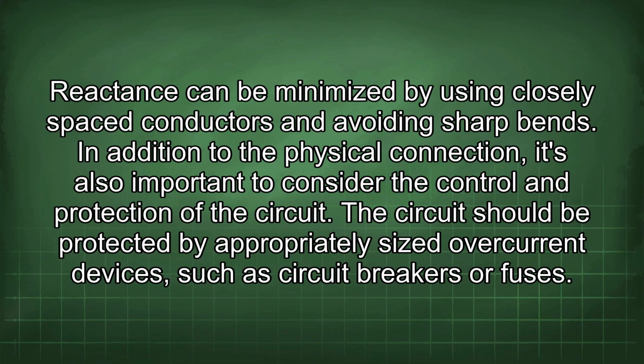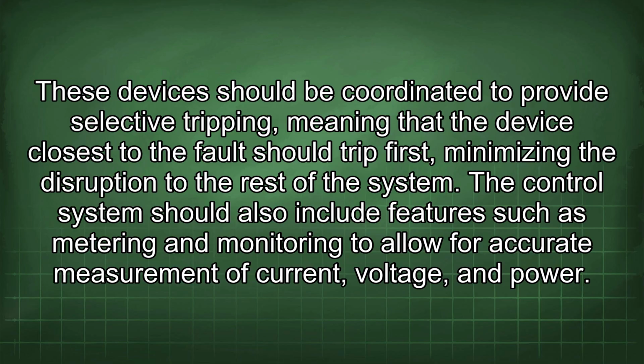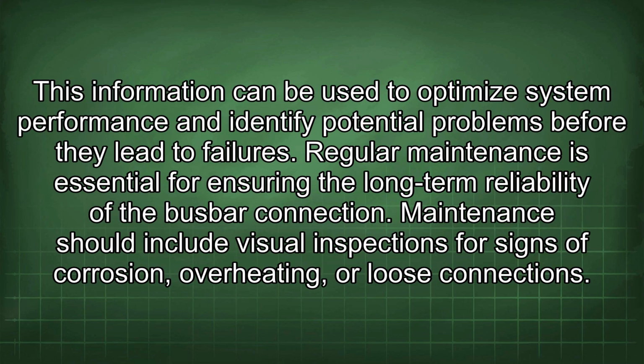In addition to the physical connection, it's also important to consider the control and protection of the circuit. The circuit should be protected by appropriately sized overcurrent devices, such as circuit breakers or fuses. These devices should be coordinated to provide selective tripping, meaning that the device closest to the fault should trip first, minimizing the disruption to the rest of the system. The control system should also include features such as metering and monitoring to allow for accurate measurement of current, voltage, and power. This information can be used to optimize system performance and identify potential problems before they lead to failures.